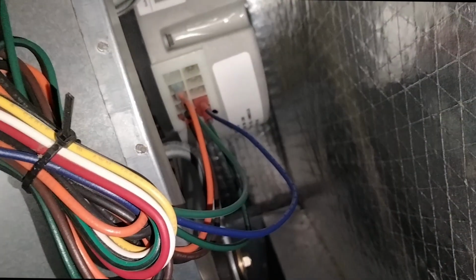then the next thing to go to, if you're hearing that click but your motor is not coming on, you're not seeing spinning, you're not hearing the motor come on, and this is an X13 motor, which is a constant torque. This one, for the most part, goes directly to power. It's always going to have a constant 240 volts on it, and then it's going to call on that fan relay, which in this case is going to go in here and call for your fan motor to come on. Now, if it's a normal PSC motor, it can be a little different, but know that if it is not getting the 24 volts, or if you're not getting the high side power, it will not come on.